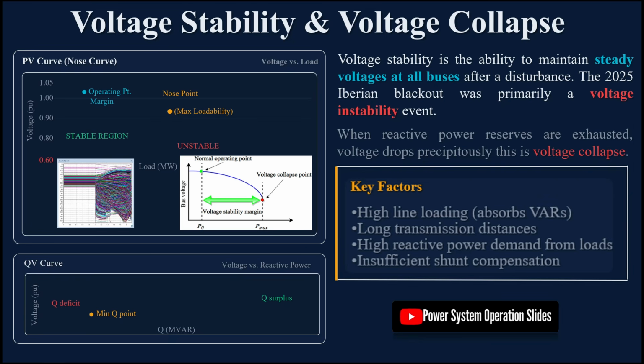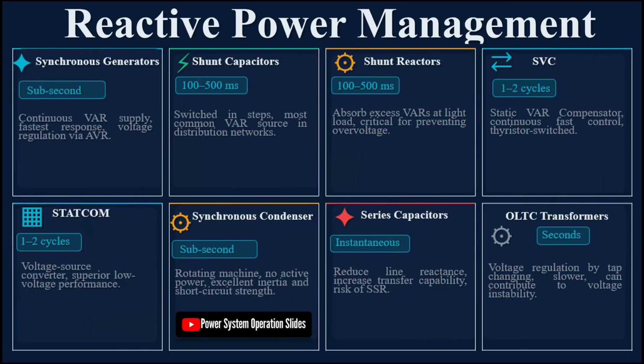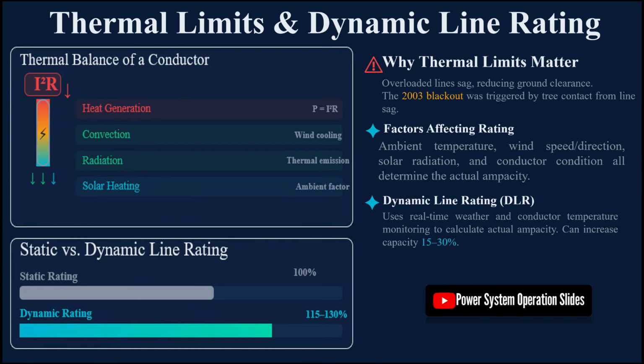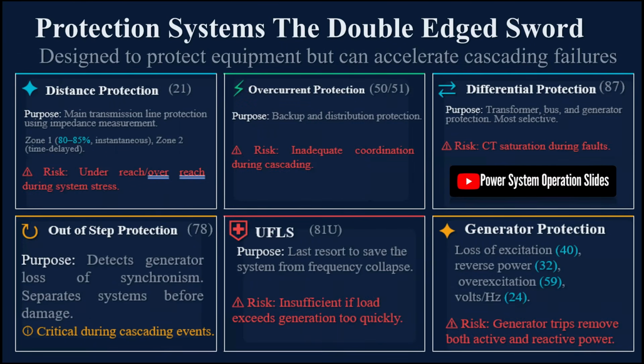Blackout development follows a specific progression from a normal state through a disturbance to the redistribution of power flows, which may eventually lead to a total collapse. Cascading failure theory explains how the sequential tripping of one component, often due to thermal overload or voltage decline, places unbearable stress on remaining elements. This chain reaction causes the system to separate into isolated islands, most of which lack sufficient generation to remain active.